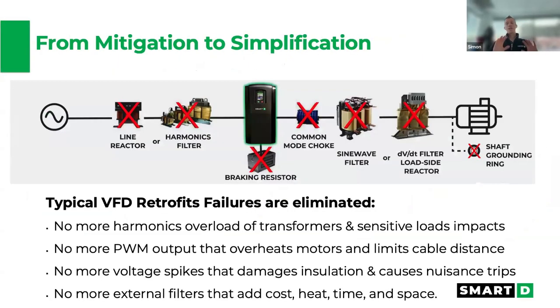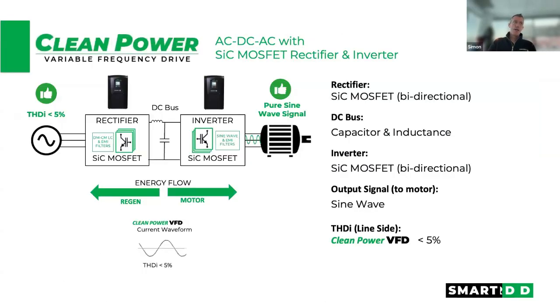So really, I love this picture. It's a great way to summarize what we do. We're going from mitigation to simplification. Take out these ifs, these buts, these "hey, my retrofit fails because of harmonics or because of the PWM output or voltage spikes." Just take that out. You don't need those external filters. You don't need those shaft grounding rings. You all have it built in the Smart D Clean Power VFD.